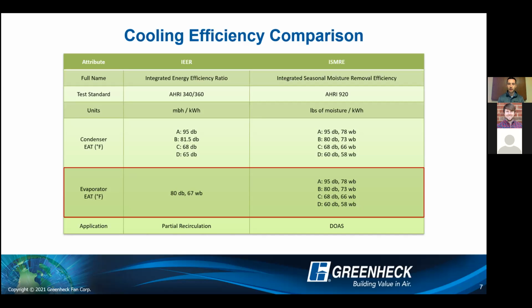If you look at the ISMRE value and the evaporator entering air temps, now you see a wide range of conditions that AHRI 920 is testing, different dry bulbs and wet bulbs, whether it's hot and humid, whether it's pretty mediocre as far as conditions being part load, or you can see all the way at the bottom at condition D, it's 60-degree dry bulb. So it's not very warm out, but there's a really high wet bulb compared to the dry bulb. So it's a lot of humidity in the air that we still have to strip off moisture. And we are trying to determine how effective we are at dehumidifying, or removing that moisture. And that's why in this ISMRE value, the units are actually looking at pounds of moisture removed per kilowatt hour versus strictly MBH. So hopefully that makes sense.